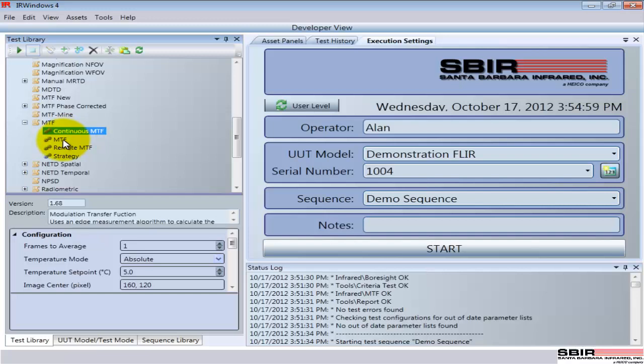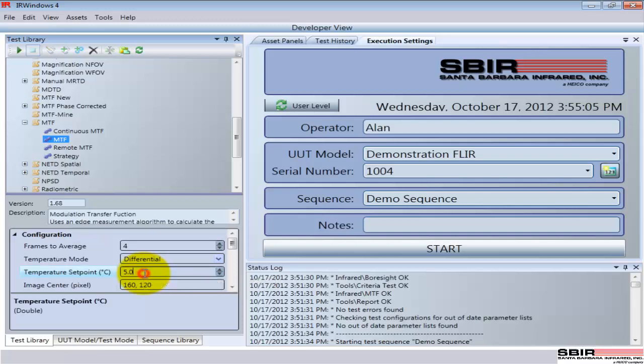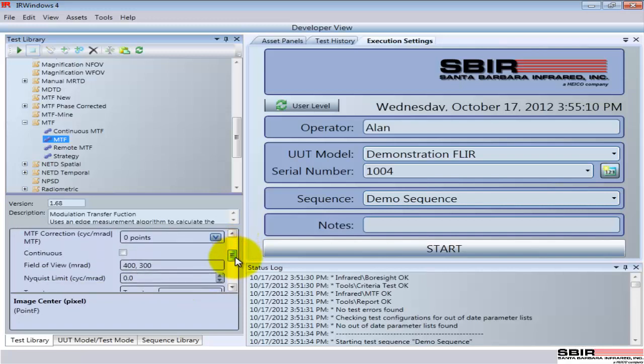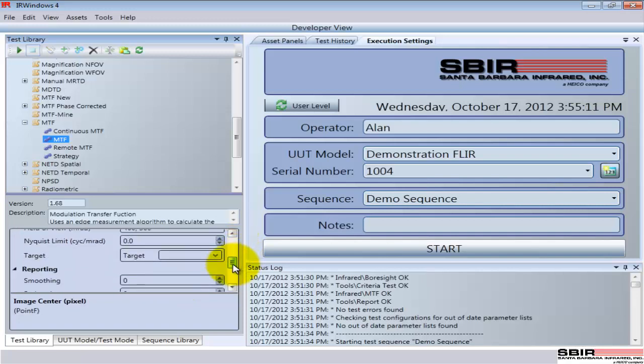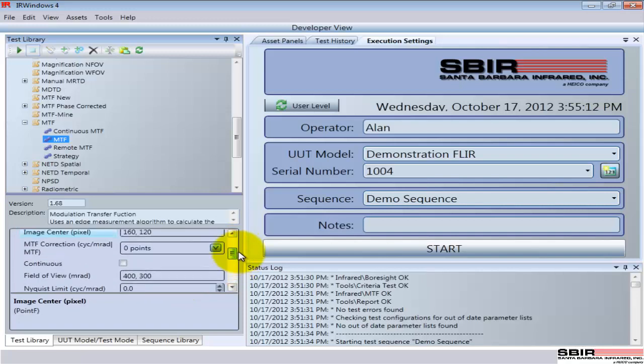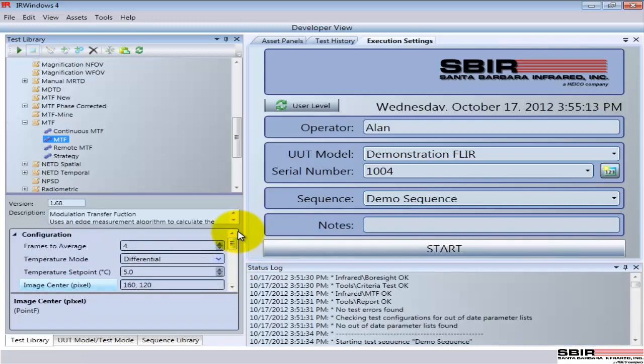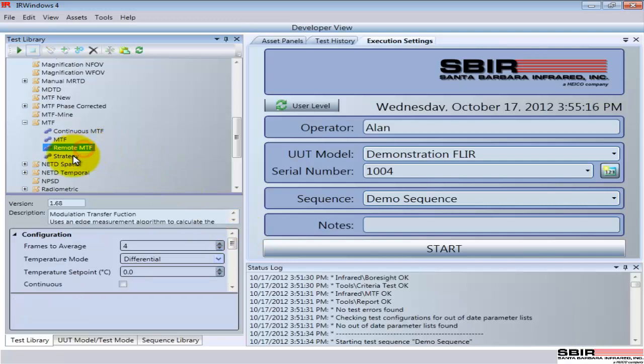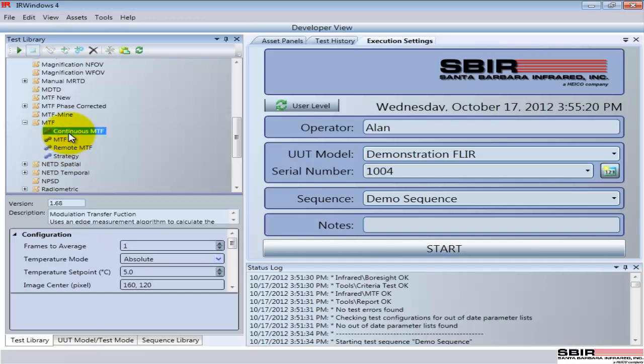And under that sort of general definition of the test, we have the specifics as test configurations. A test configuration holds the details of how we're going to run that test. Like in this case, we're going to average four different frames, we're running at this particular set point, meaning the black body will be controlled to that temperature. There is the center of the image, the region of interest that we're going to be collecting our data from, the target that will be run. All the details of running the test are stored in separate configurations.